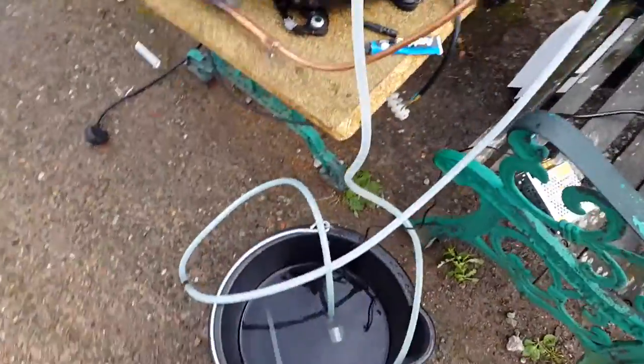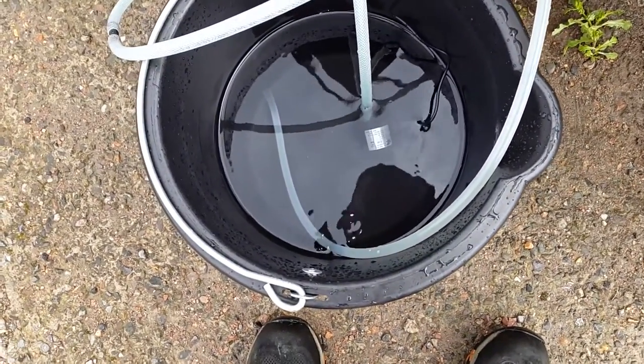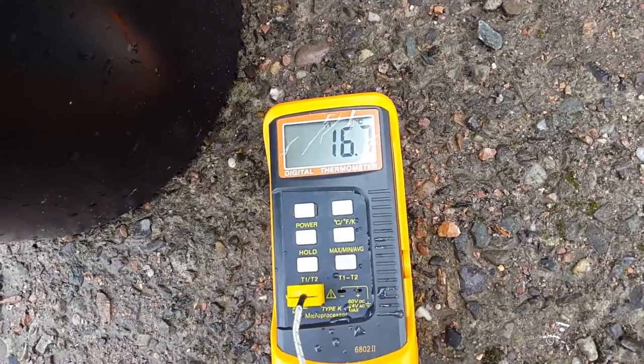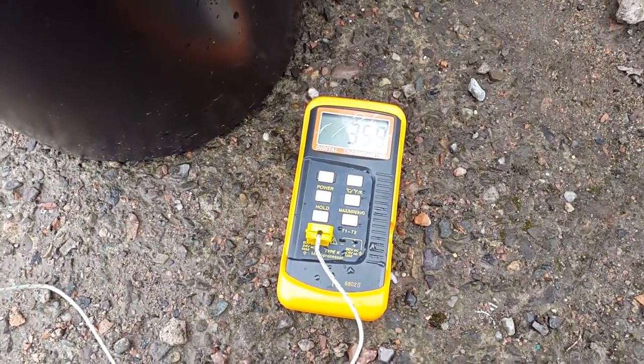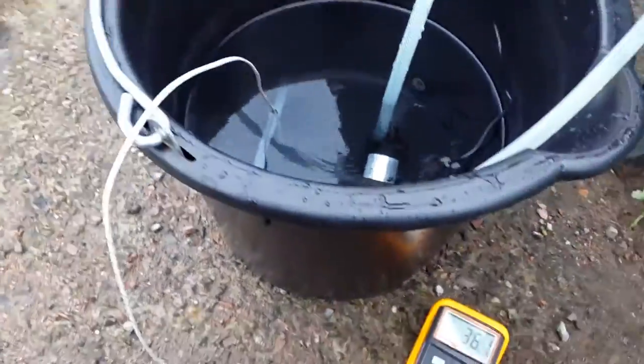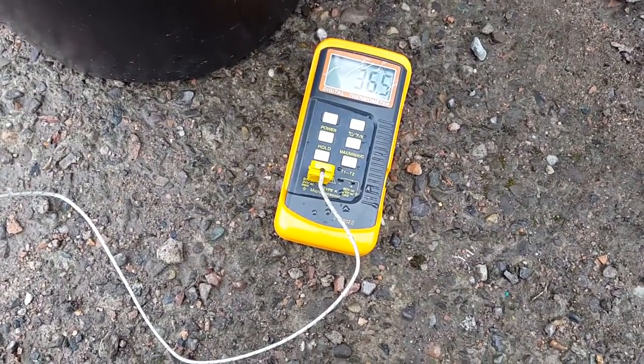Today I'm going to test out this heat pump and see how long it takes to heat this water up to 35 degrees Celsius. I'll just run the experiment and show you what my findings are. Starting at 16.7 degrees C. In 7 minutes and 31 seconds we got the temperature up to 35.8, roughly 36. So it seems quite powerful, and I'll go and do some calculations to figure out how powerful it actually is.